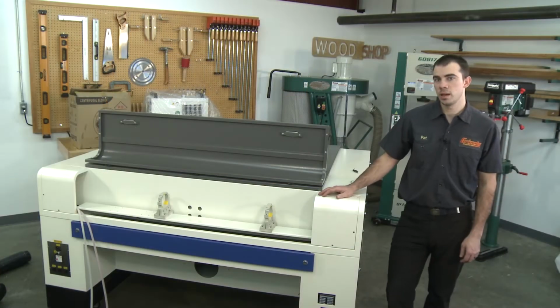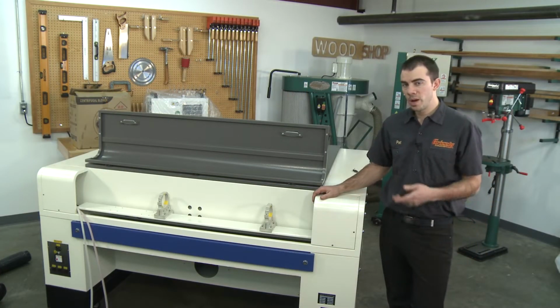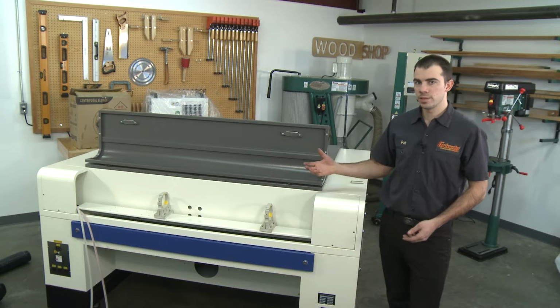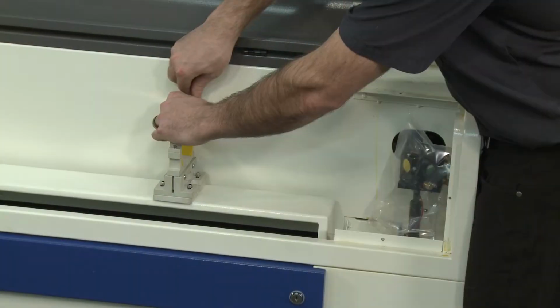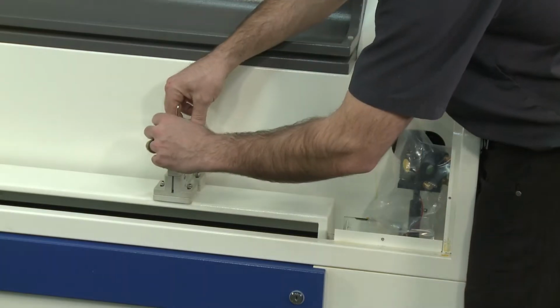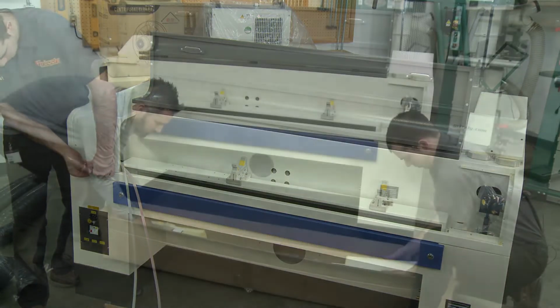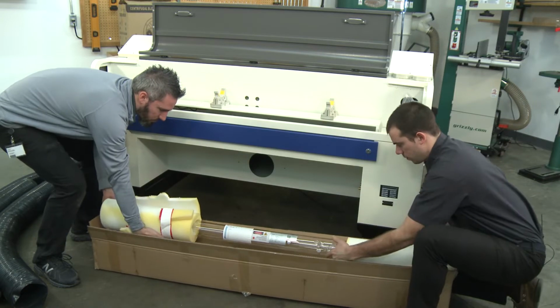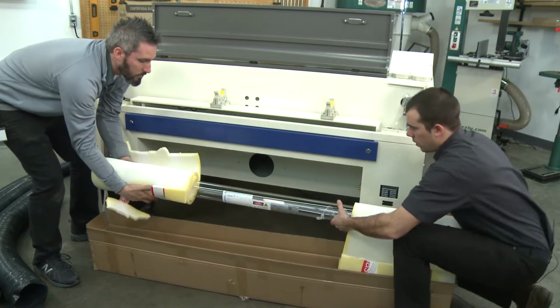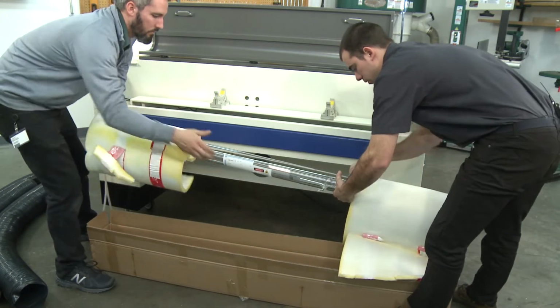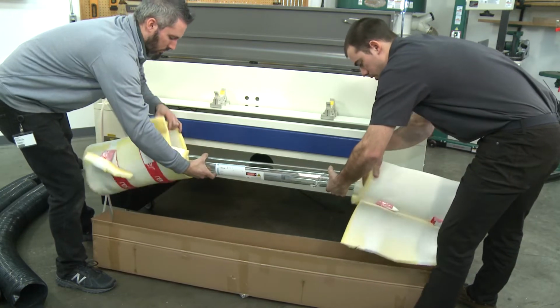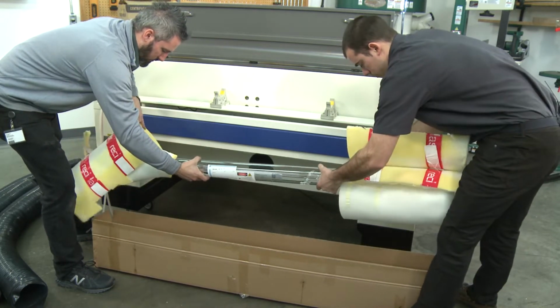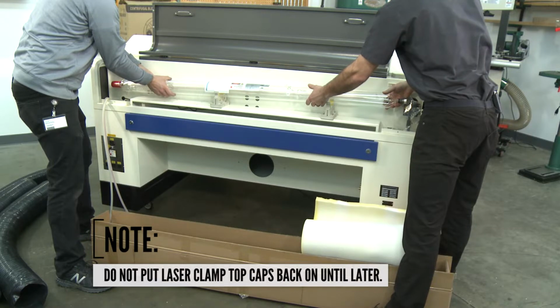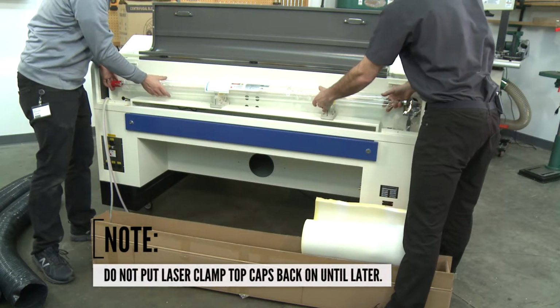The first step to setting up a G0874 is going to be to unbox the laser tube and get that in place. In order to do that, you need to remove both end caps, remove the top caps for the laser clamps as well, then the laser can be dropped in place. The laser tubes come with foam wrapped on each end of the laser. The next step is to cut the tape free, remove the laser tube from the box, get rid of the foam. I highly recommend using two people to do this. This is the most expensive part of the machine and they're very fragile.